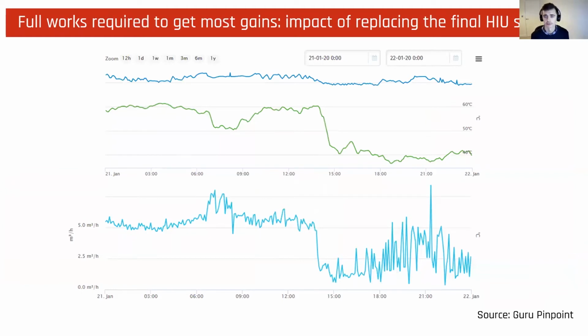And so looking at the impacts of the works, on this graph here we show the plant room flow temperature in blue, the return temperature in green on the top graph, and the flow rate in light blue on the bottom graph. Now, the system's currently operating at 70-degree flow temperature, and this graph shows the final HIU being replaced. What can be seen here is we're getting 60-degree returns, but as we bring in that final HIU, the return temperature drops by 20 degrees.